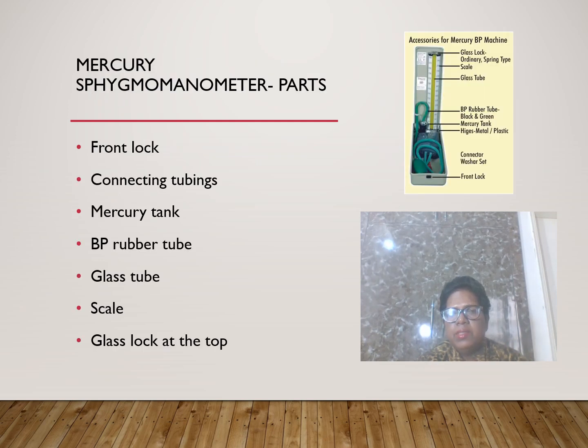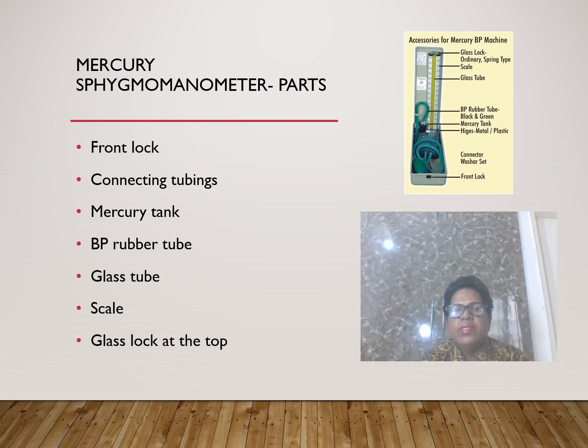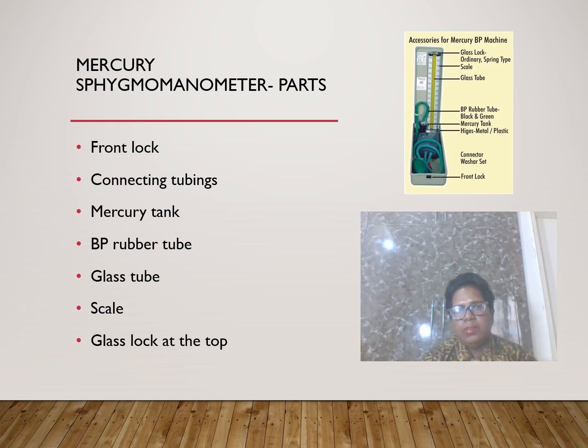A mercury sphygmomanometer is the instrument used to take BP. Its parts include: a control lock, connecting tube, washers, mercury column, mercury tank, rubber tubing, glass tube, and a calibrated scale on the glass tube.